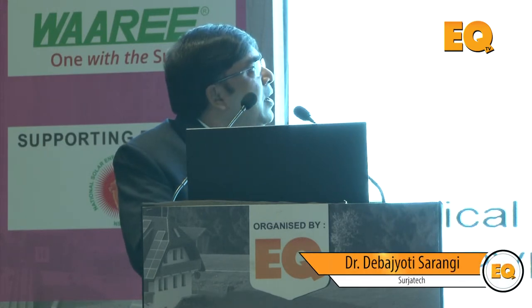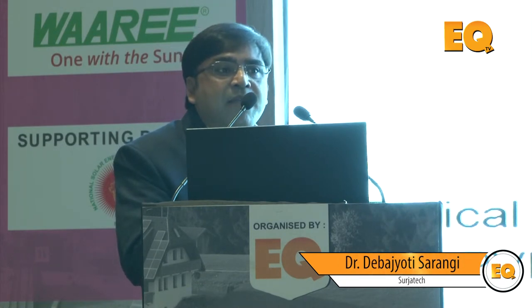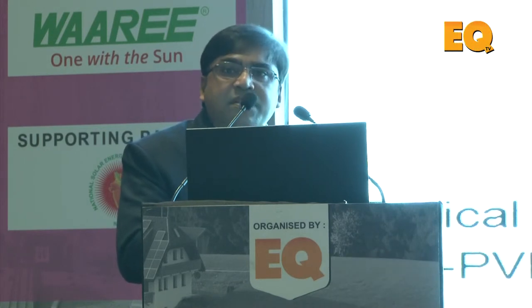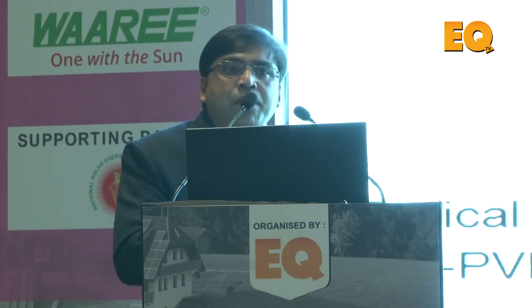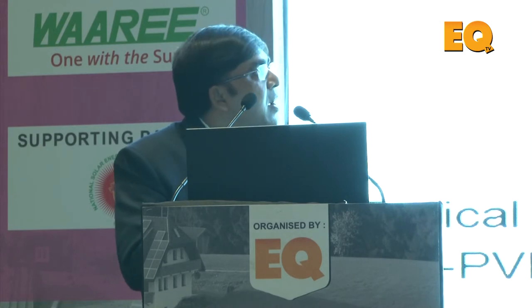And in the last 10 years, this 3% degradation is because of the anti-reflection coating on the glass. Anti-reflection coating will never stay a long time. Within 2 to 3 years it will come off, because it is on the top of the glass. So there is a 3% degradation.